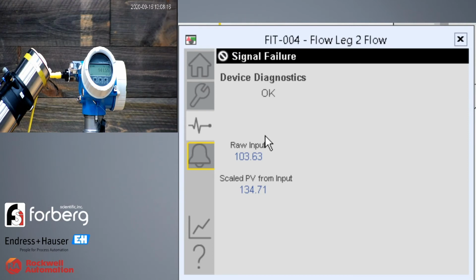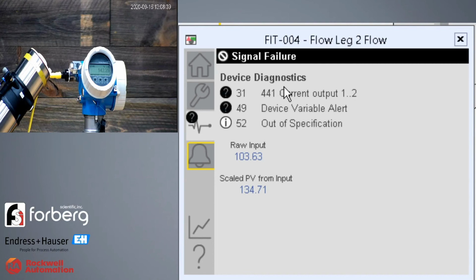But after a few seconds here, through the benefit of HART, what you see is the diagnostic information that was provided as the process flow exceeded that range that we talked about earlier, when the device was configured from 0 to 130. Again, both the values and the descriptions that are device specific for this particular E+H device are shown.